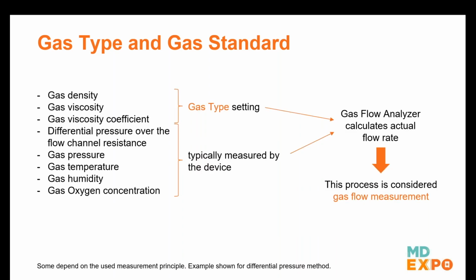How critical is it to replace that O2 sensor on the gas flow analyzer? I know it has like an expiration date, but does it vary a lot if it expires? Yeah, it's more important that you calibrate it, and if it fails calibration, replace it.